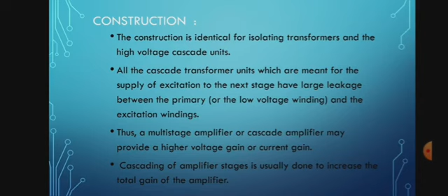A high voltage connection from the first transformer winding and the excitation winding terminal are taken through a bushing to the second transformer. In a similar manner, the third transformer is kept on insulators above the ground at the potential of V2 and supplied likewise from the second transformer. The number of stages in this type of arrangement is usually 2 or 4, but very often 3 stages are adopted to facilitate 3-phase operation, so that root 3 V2 can be obtained between these lines.